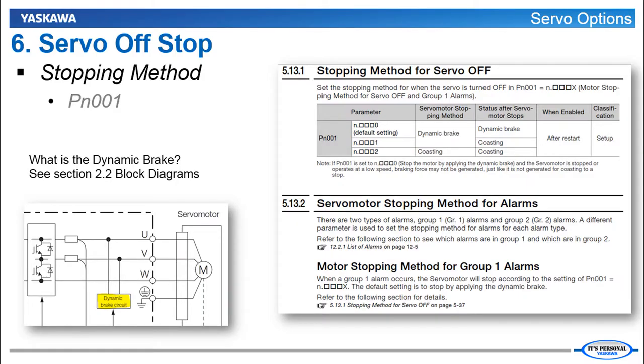This is very similar to a safety stop but it does not use redundant hardware inputs. One of the most basic options for stopping is how does the motor stop when the servo turns off during motion. If the servo turns off during motion you obviously can't have a controlled stop with torque. So it's a choice between coasting to a stop and using what's called a dynamic brake which is a shorting of the motor terminals through a resistor circuit that causes the motor to stop more quickly than it would with friction alone as it coasts to a stop. By default you see that we do use that dynamic brake circuit to stop very quickly. And you might change this to a coast to a stop option if the machine stops too abruptly when the servo on signal is removed during motion. Or if you get an alarm, a dynamic brake overload alarm with larger loads and higher speeds. And keep in mind this is not a situation that should be happening regularly.